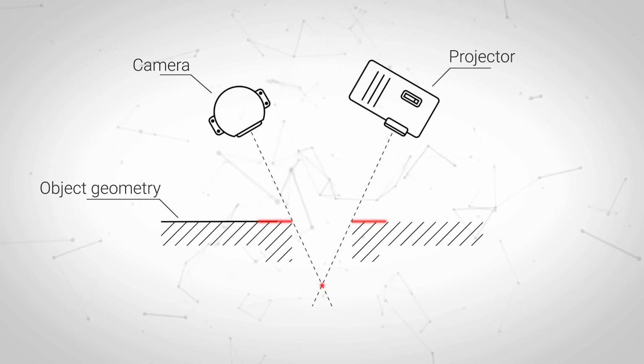Another thing to keep in mind is that the SLS system creates a 2D field, not 3D. The 3D capabilities of an SLS system are created by either having two opposing systems or by recording the data points as the camera moves and stitching those capture points together. Let's look at a few pictures captured this way.